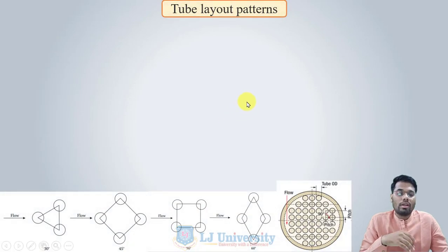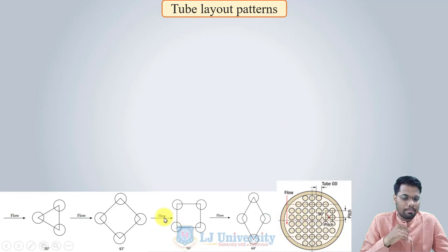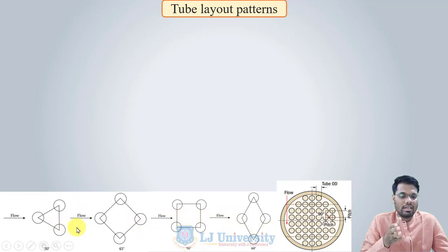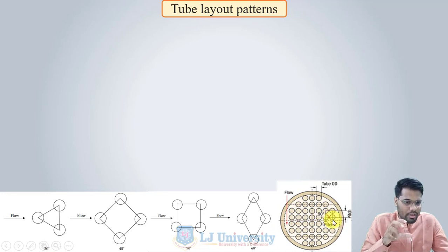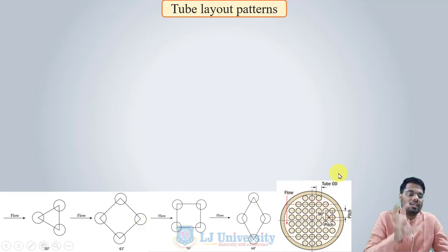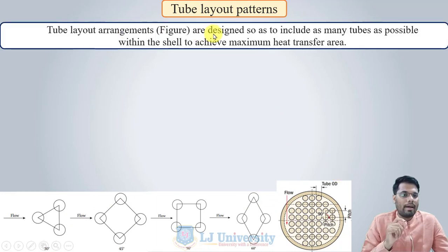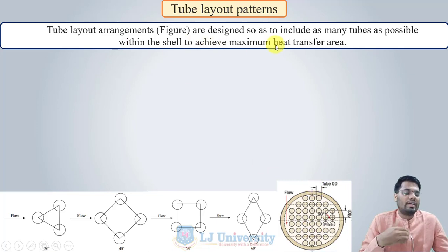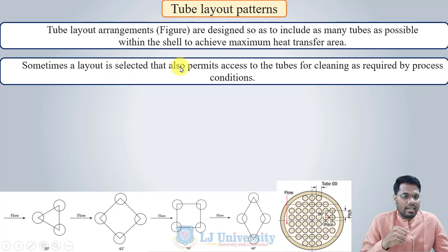Tubes are generally arranged in patterns at angles of 30°, 45°, 90°, and 60°. As seen in the figure, the circle represents the shell and the smaller circles represent the tubes inside. In one layout the centers of four tubes are at 90° to each other. Tube layout arrangements are designed to include as many tubes as possible within the shell to achieve maximum heat transfer area, and sometimes the layout also permits access to tubes for cleaning as required by process conditions.